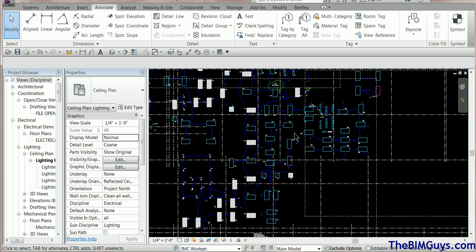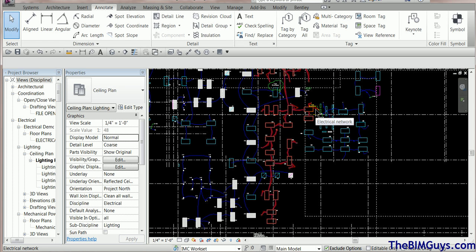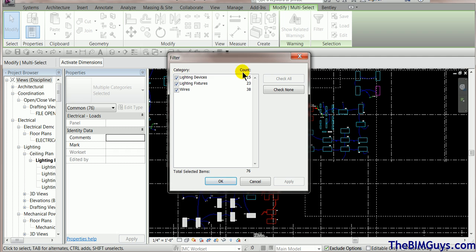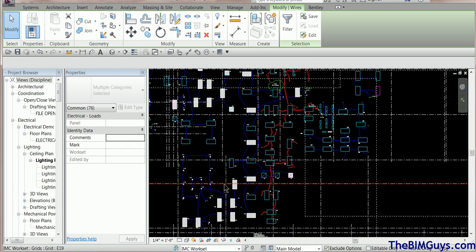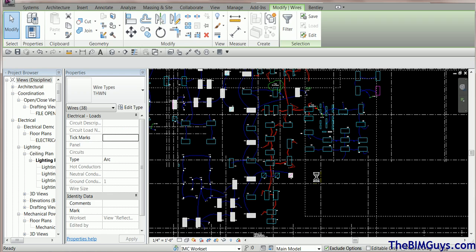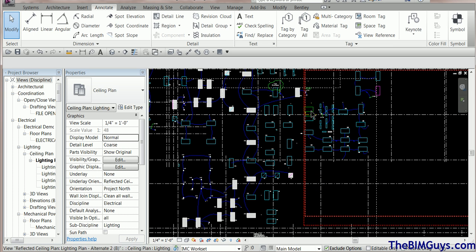Sometimes the fix is just deleting the wire and redoing it — and I know that sounds a little crazy. That circuit picks up some sensors and things that look fine. Now I'll hit Filters, select just the wires, and delete them. I know you're going to freak out because I'm deleting all the wires, but Revit still knows everything is wired together because the wires are just a secondary graphical representation.